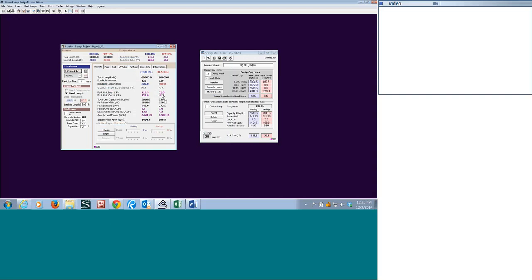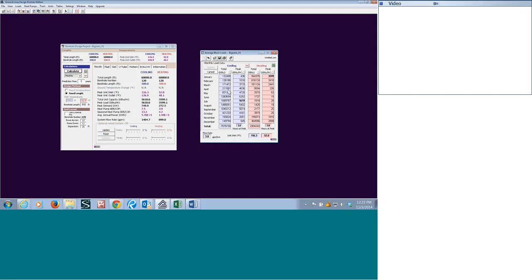We're not concerned about the heating side. We obviously have a cooling dominant load. So let's go back to our loads here, and I want you to keep in mind these values for the peaks and the total duration loads. So looks like we're going to have to look at adding in an auxiliary cooling tower of some sort or equivalent cooling device. So we can use GLD to determine that auxiliary capacity that is necessary. So we can go down here on cooling to our peaks, and I'm going to take this up to about 30% of the peak cooling load. There we go. I'm going to select update, which will modify this load profile.